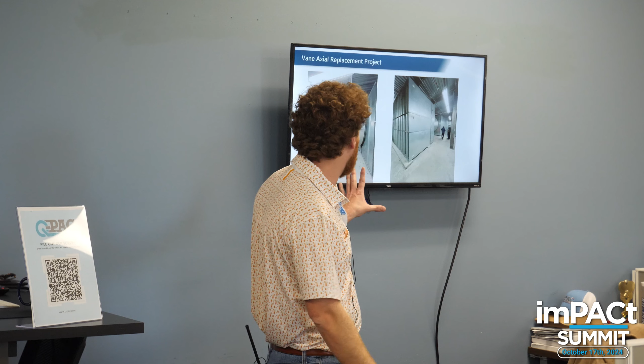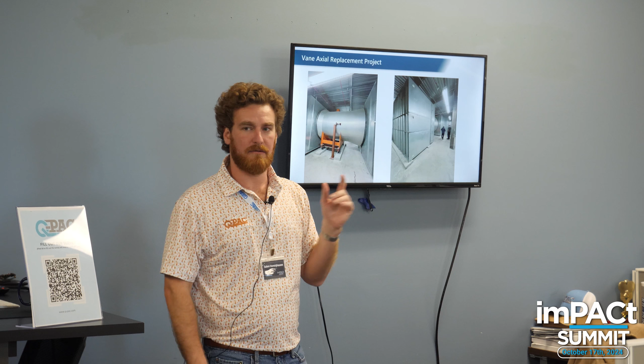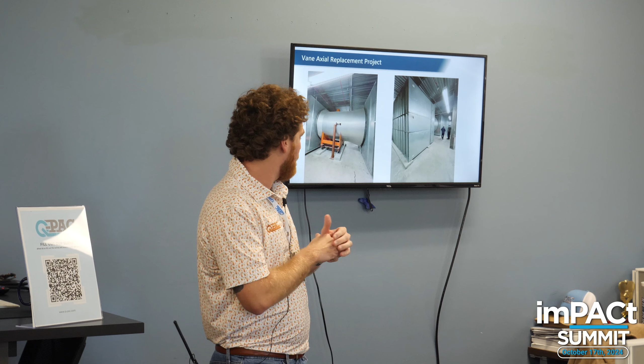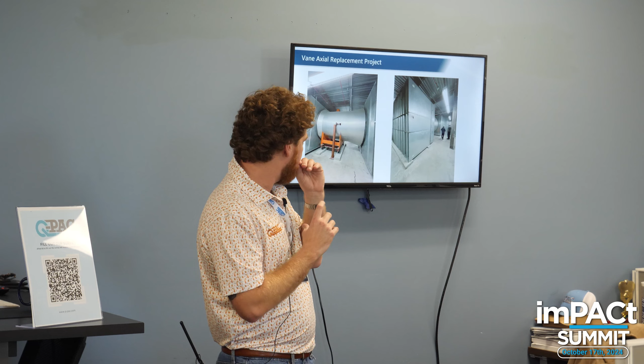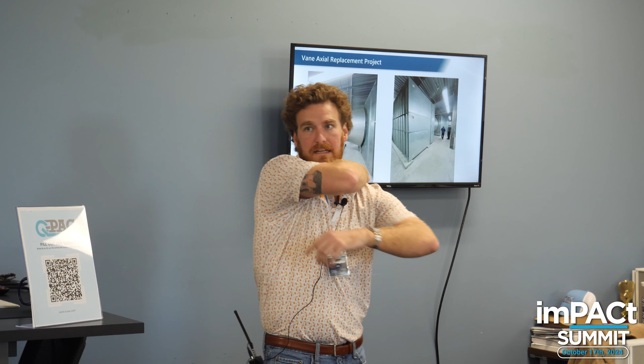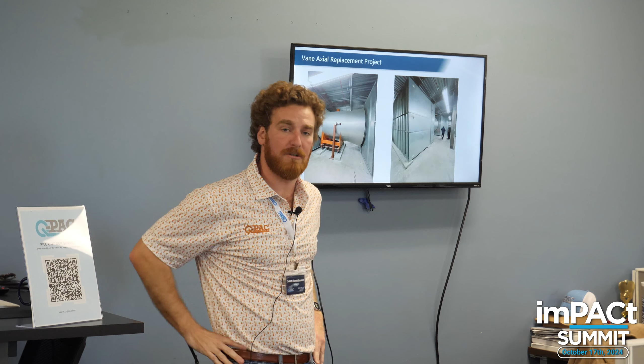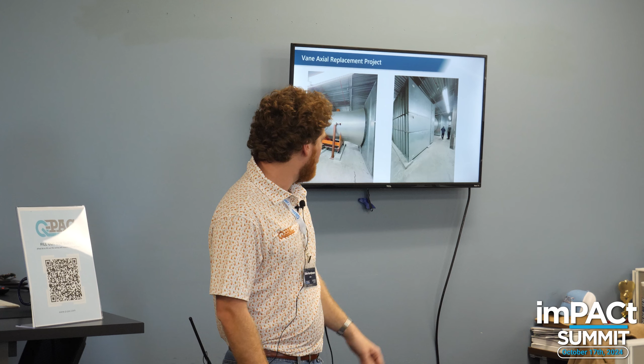Here's another one, kind of a special case. You're not going to see a whole lot of these, but we can potentially do a really large vane axial replacement. I think it was a vane axial fan that John and Tom were talking about in their presentation earlier, but it wasn't quite like this. These really large ones have a really high face velocity, a really high velocity of air through the fan, and in a lot of cases they're pretty far away from the cooling coils because of that, and there might not be as much space in those areas. So if you can get closer to the cooling coil, you can typically use a Q-PAC fan pretty effectively, and try to get as close to that cooling coil as you can. There may be some additional sheet metal you have to do, you might even have to build a little plenum, but we can retrofit vane axials as well. This was just a large one that wasn't really implemented, but we think it should have been.